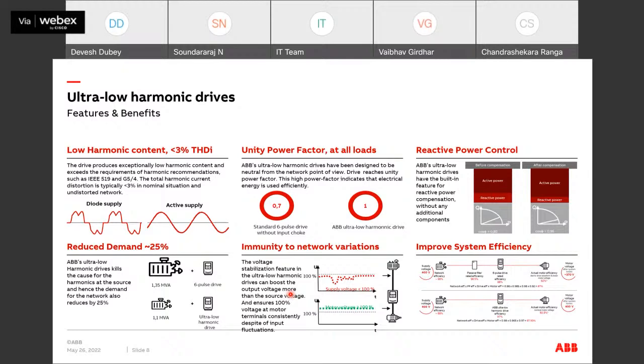Improved system efficiency: when you have a standard solution, a diode-based drive with a passive filter, and you have 400 volts as input, the output voltage which goes to the motor may deteriorate by a certain percentage. While if you remove the passive filter and use an ABB or any active front-end drive, the motor voltage will be 100%, since the drive itself has the capability to boost the voltage. From an efficiency point of view also, there is 1% or 2% better efficiency because we are removing the passive filter, which is additional equipment going into the electrical network.